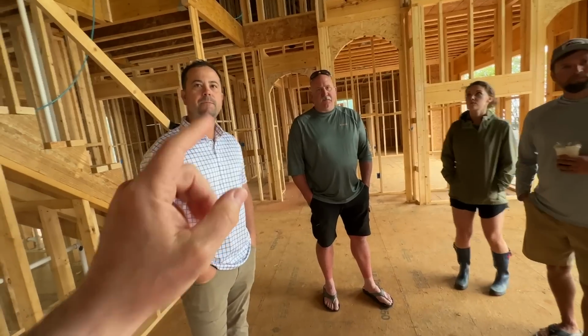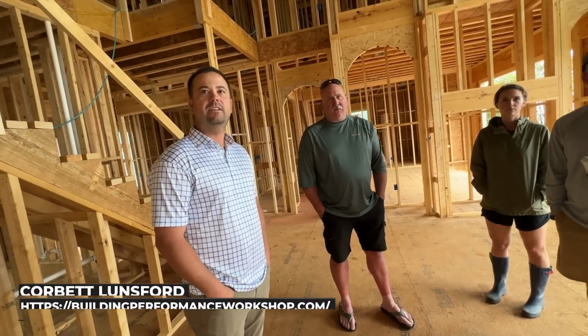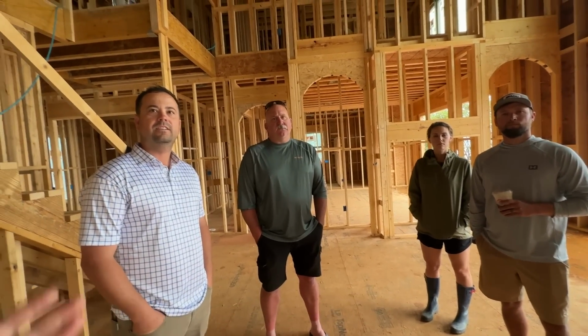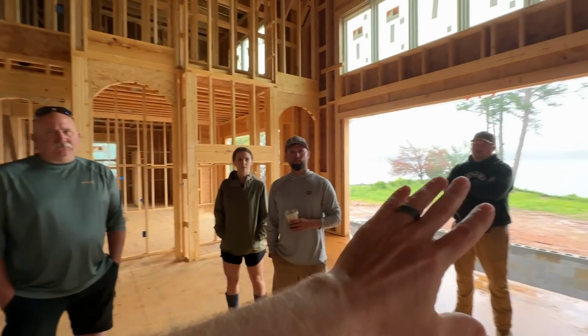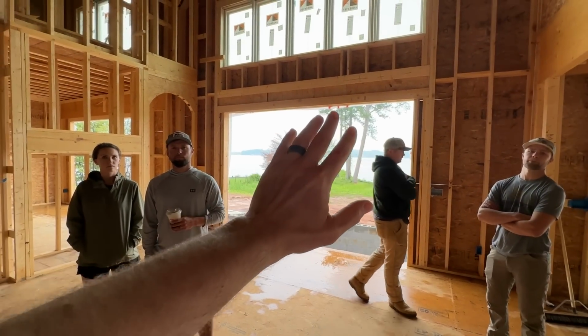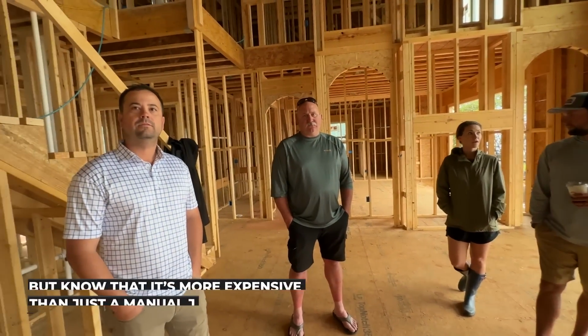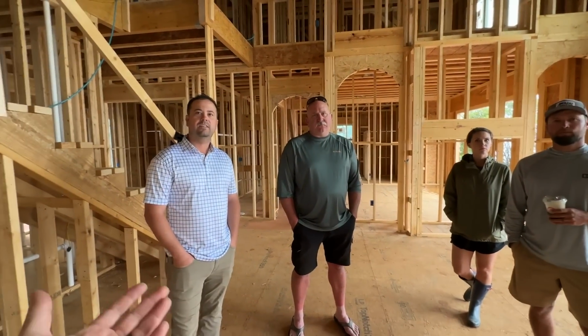That's great to hear. So this house, I'd recommend getting a Manual J on the house. And I've got two or three friends I could hook you up with, a guy named Corbett Lunsford or Allison Bales at Energy Vanguard. We're talking 1,000, or retail might be more than that, but 2,000, let's say. And they would do a load calculation where they would say, okay, these doors, these windows, they're facing this direction. This is the insulation value of the glass. This is the solar heat gain coefficient. And then they'd calculate how much load is coming through that wall so that you could actually figure out the exact amount of tonnage of air conditioning you need and the number of BTUs your furnace needs in the wintertime.